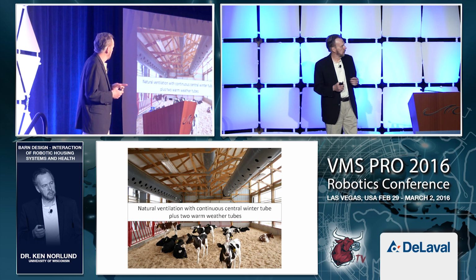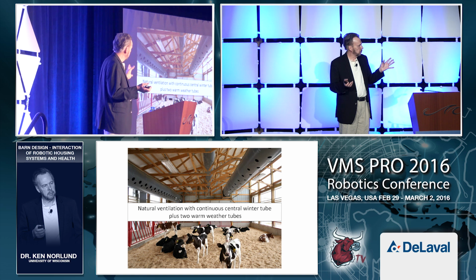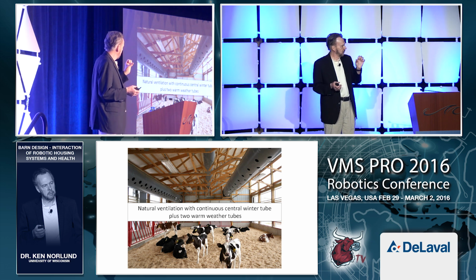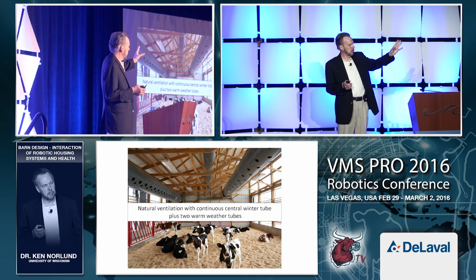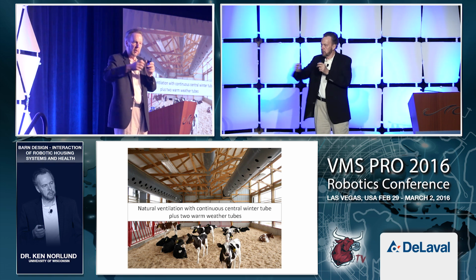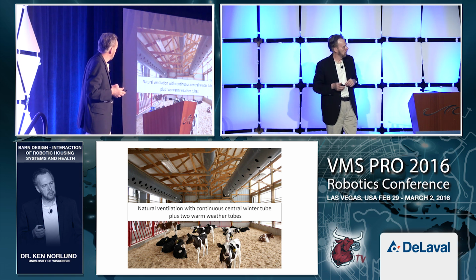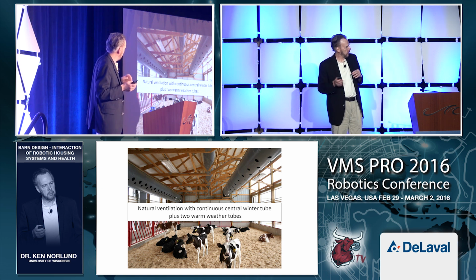Never, ever stops. Then there's 2 additional ones that are used, in this case, for other purposes. And they're controlled by thermostats. And so as the barn gets warmer, actually there's also wind control on that too. If it's windy, they don't come on. But if the winds are slow or non-existent, and in an 8-shaped barn, depending on wind directions, the central work alley interferes with the winds to some part of the other barn. So each one is controlled individually. And if it gets still and warm, one or both of these other supplemental fans come on.